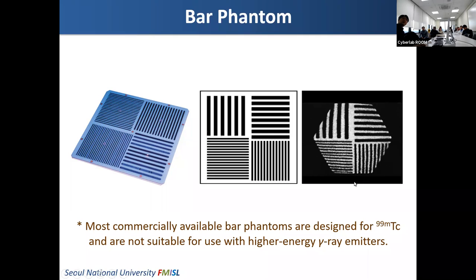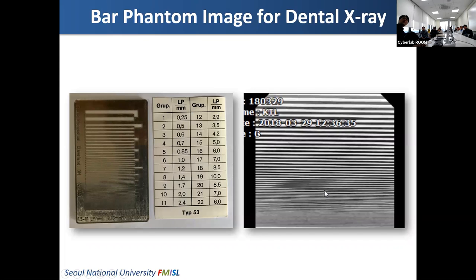This is another bar phantom — a very fine bar phantom used in x-ray CT. When scanning, at some point we cannot distinguish the bar phantoms. Using this kind of phantom, we can estimate what the spatial resolution is.